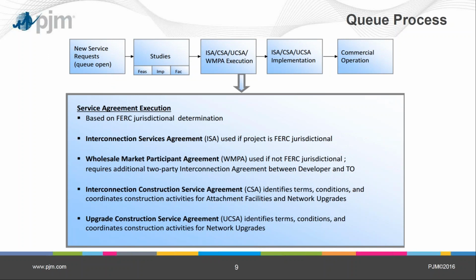After you go through the study process, there is a service agreement that needs to be executed, and for energy storage it's either in the form of an interconnection service agreement or a wholesale market participation agreement. The difference between those two is primarily over jurisdiction. A FERC jurisdictional project - anything connecting to transmission level voltages, or a line that has previously had a wholesale project interconnected to it - is considered FERC jurisdictional. If you're connecting to a distribution facility that has never had a wholesale generator connected to it previously, then you're going to sign a wholesale market participation agreement.